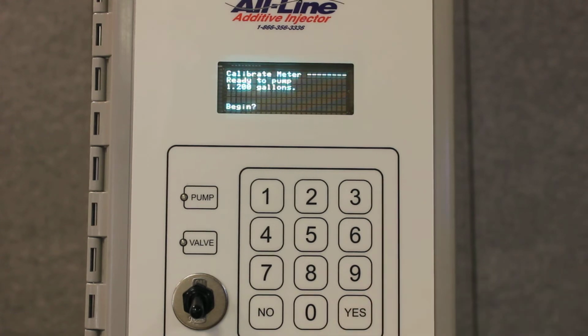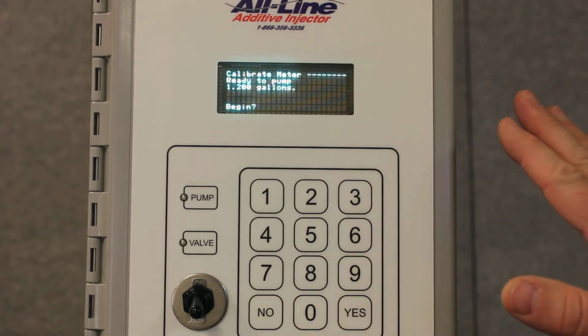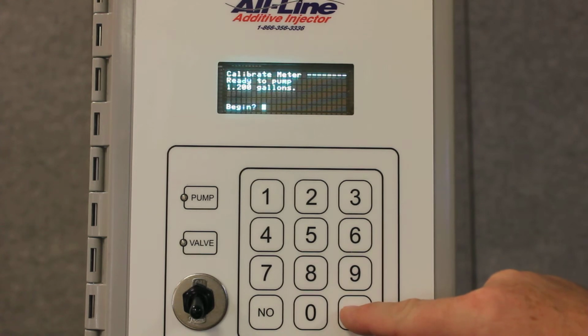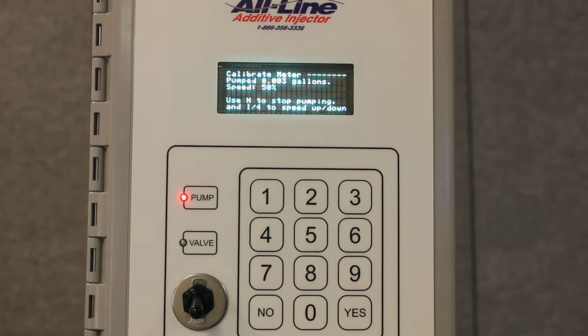So we'll tell it to pump 1.2 gallons. It doesn't start the pump until you hit begin. Now the pump is running, and we're dispensing the additive through the calibration hose into a container. We see that it's counting, which tells us right off that the pump is primed and the meter is not jammed.